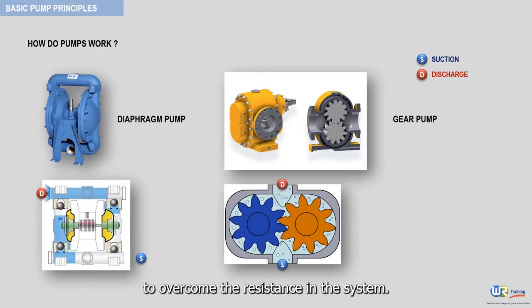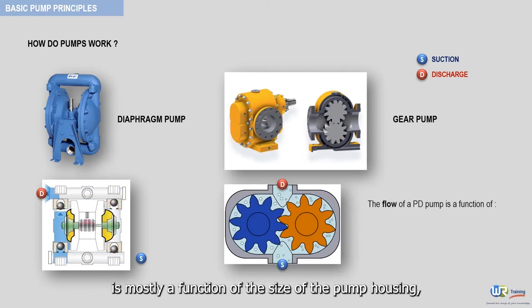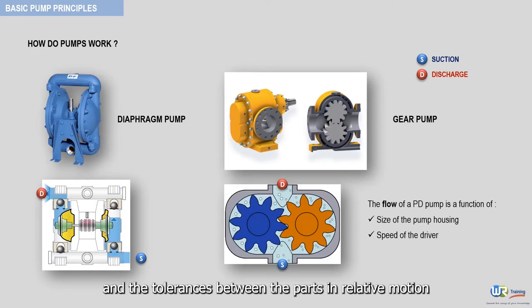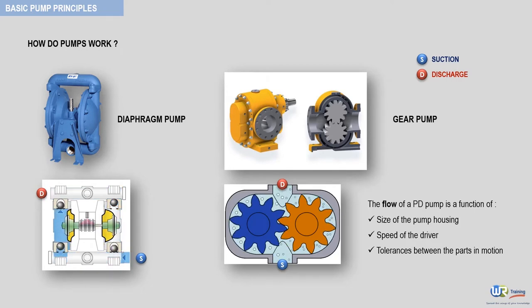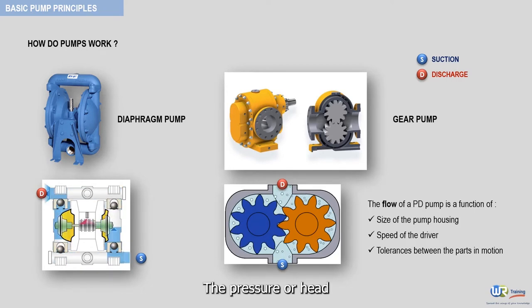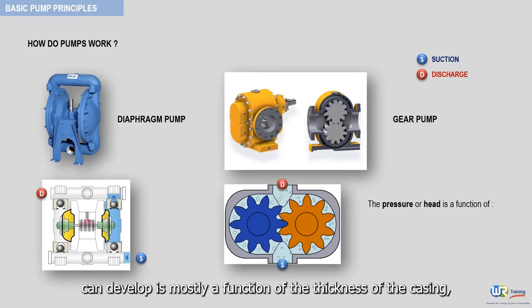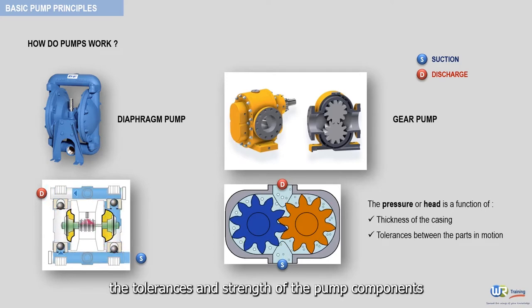The fluid is expelled into the discharge piping, prepared to overcome the resistance in the system. The flow that a positive displacement pump can generate is mostly a function of the size of the pump housing, the speed of the motor, and the tolerances between the parts in relative motion. The pressure or head that a positive displacement pump can develop is mostly a function of the thickness of the casing, the tolerances, and strength of the pump components.